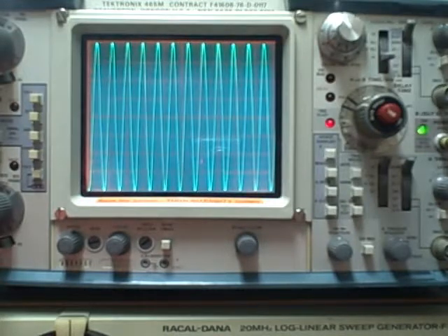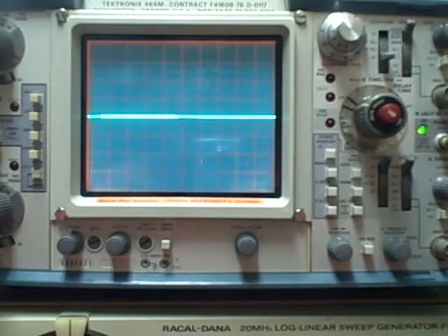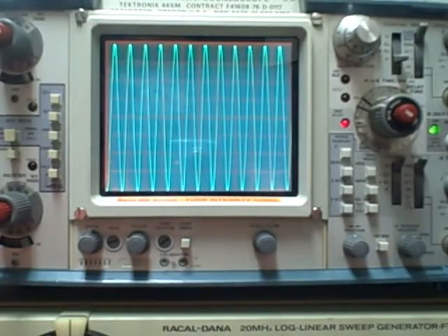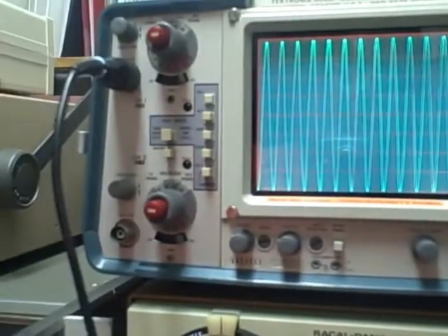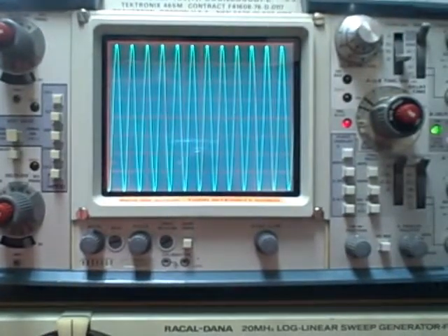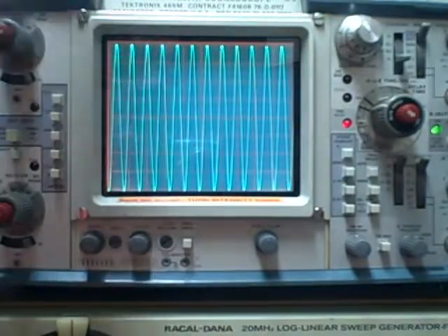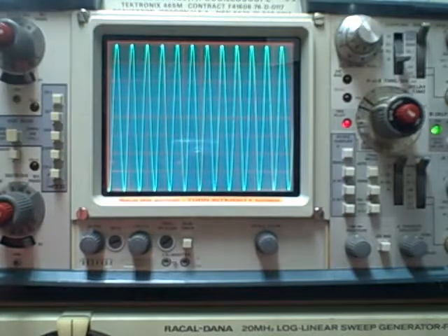We're going to move to channel 1. So give me a moment. Okay, we're on channel 1, and we can see our probe's been moved to 1. We have 1 depressed here. We're on 5 volts per division, so that means we have 20 volts up, and we are feeding 14.1421 volts RMS from the Fluke and getting it. So that's good.